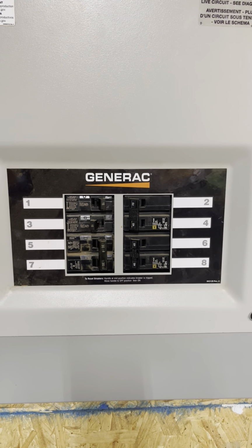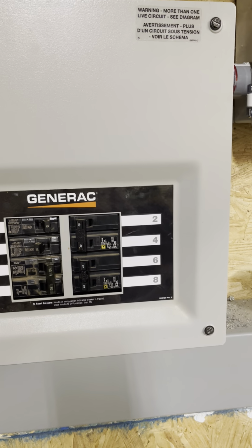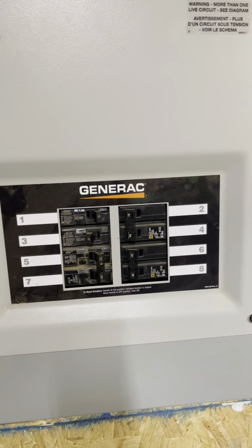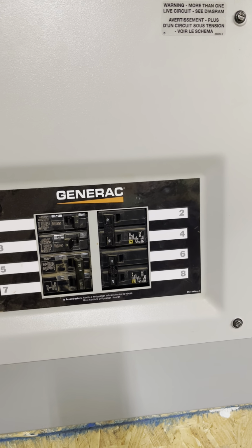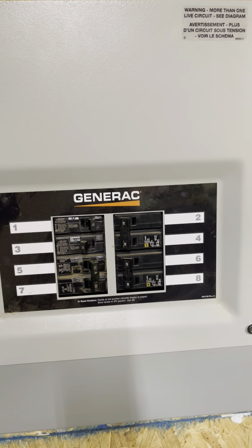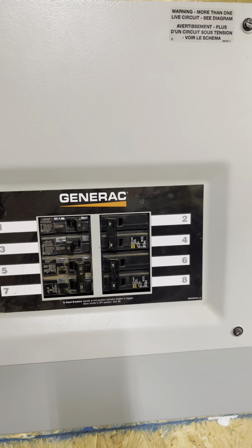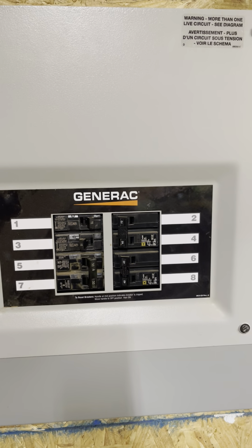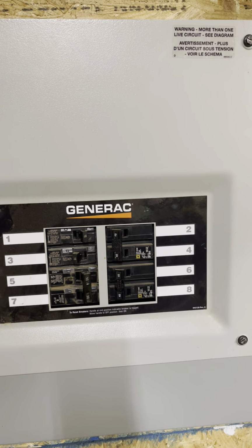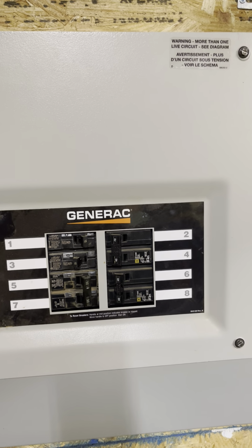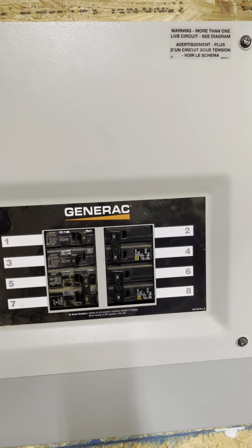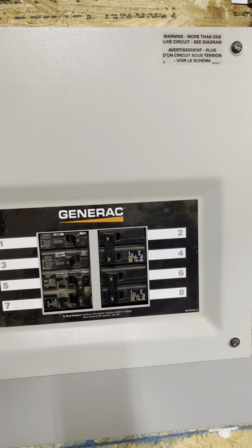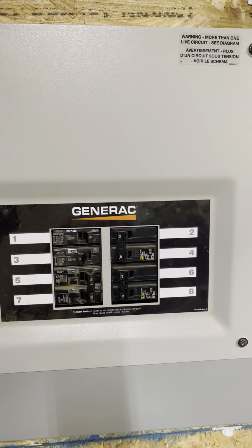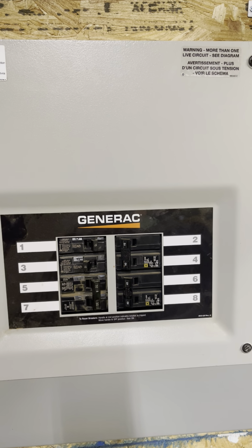So the thing I learned with the auto start Generac is that it has voltage sensing. The voltage sensing is actually located within the generator itself. So when the grid fails, it says, hey, there's low voltage, I need to start. I start, and it starts to feed. The XP6000s have the ability to have a generator input, but it won't fire the auto start on this panel. So the generator would sit there and run 24/7, and the XP6000s would charge the batteries and run off of the generator even if there was solar available. That wasn't really the most economical or the smartest thing to do.